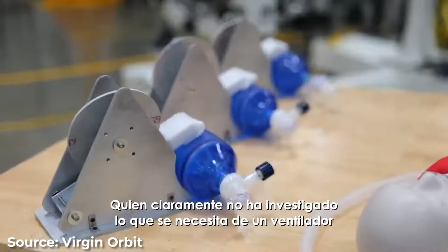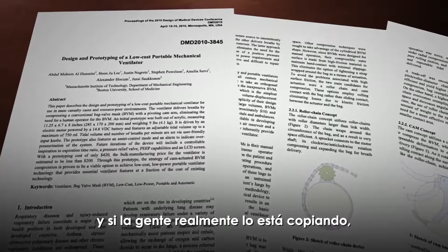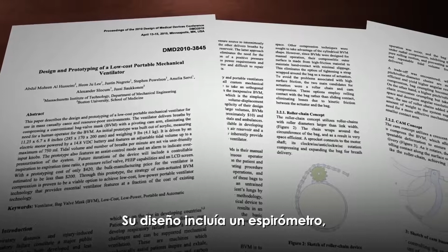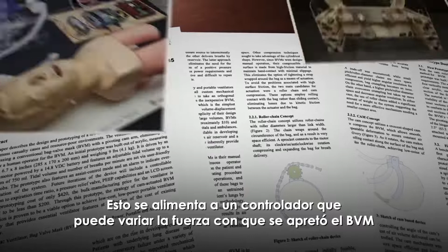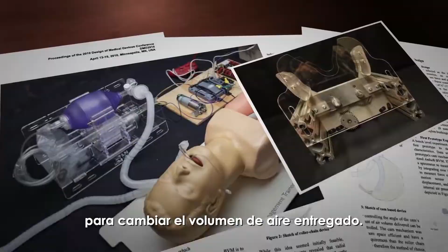As far as I can tell, the earliest design that proposed using these BVMs was from an MIT student project from 2010. This paper has been online that entire time, and if people are truly copying it, they're leaving out some clever design ideas that make it more functional. Their design included a spirometer, which measures the airflow rate out of the BVM. By integrating this value over time, they can calculate the volume of air delivered. This then feeds into a controller which can vary how tightly the BVM was squeezed to change the volume of air delivered. This gives the device a nice range of tidal volumes ranging from 200 milliliters to 750.